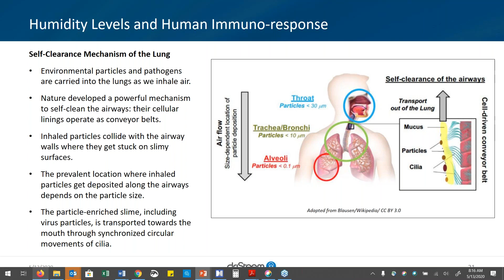Note Iwasaki also demonstrated that a 40 to 60% RH reduces infectivity. If you look to the fourth chart D, you can see that a less than 1 micron fraction is most infective from 10 to 30% RH and least infective at 43% RH. Both Iwasaki and Marr have demonstrated that an optimal humidity level inactivates the viral nuclei. Maintaining an optimal humidity level reduces the virus's viability in the environment. This can be both airborne as well as on a surface. And a number of studies have shown that between 40 to 60% RH provides the greatest level of inactivation of the virus, meaning that the virus is no longer a concern to us.